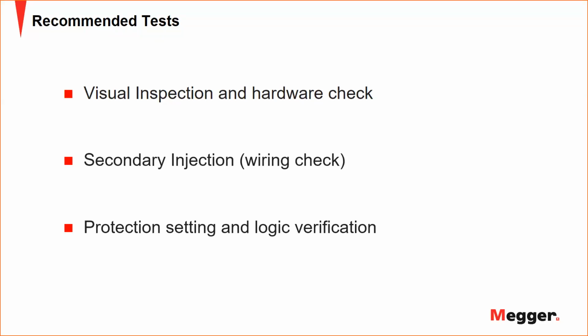And also, when we configure our outputs from the protection element into a real relay context, we verify that the logic inside the relay is tripping correctly. Any conditions that we need to satisfy are available there as well. So most of the testing will be done in the third part, where we test the protection setting and logic verification.